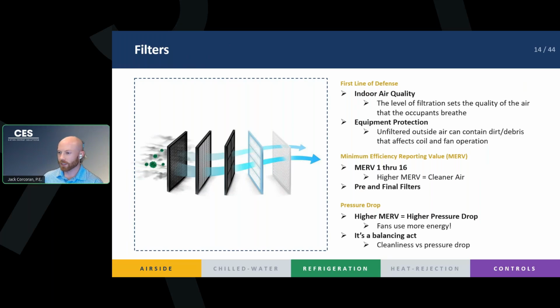Also, just inherently, higher MERV is going to have a higher pressure drop. So it is a balancing act, right? Why couldn't you just get a MERV 16, MERV 13 filter every time, right? You'd have the super clean and high quality indoor air, but you have a higher pressure drop and you're using a lot of energy, right? So it does become a balancing act, and it is all about what your project requirements are.